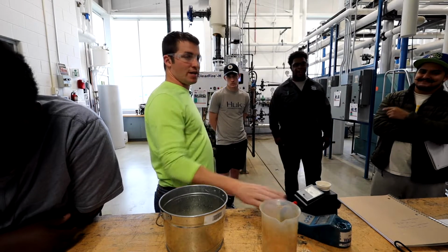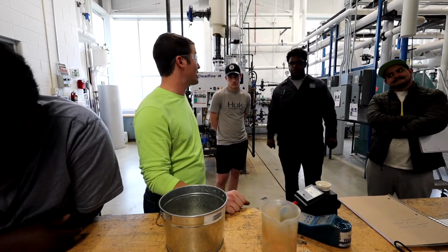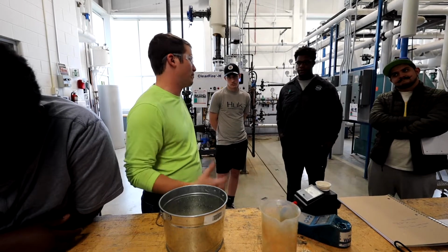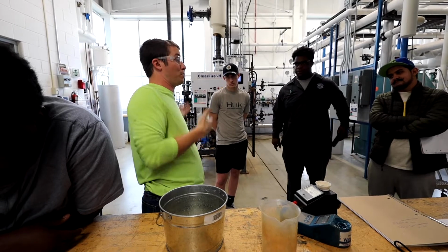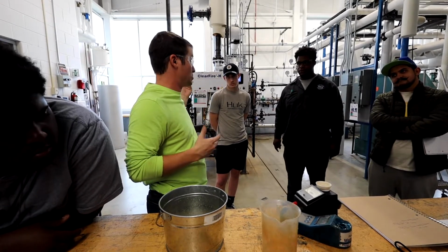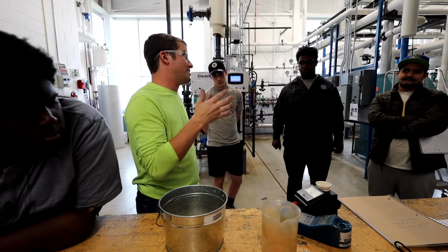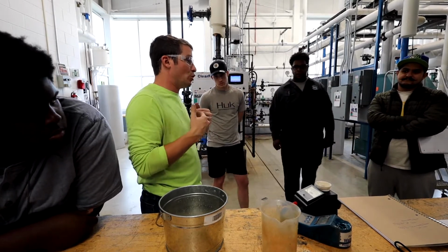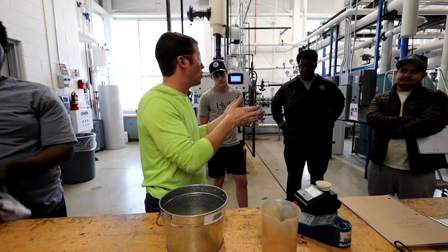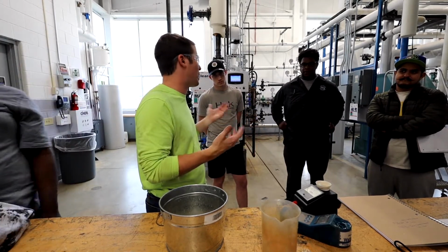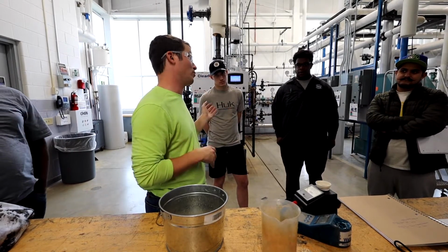So in your feed water tank, it's gonna vary. I would say 60 is great. Okay, that's awesome. If it was 150, I would say, if it was 300 in your boiler, I would be like, well, that's okay because it doesn't really run, right? So every location, it's going to be different. And that's where you're going to look for me or someone like me to tell you what those ranges are going to be, based upon how your system runs. Every single plant's different. Some run great, some don't run so great.